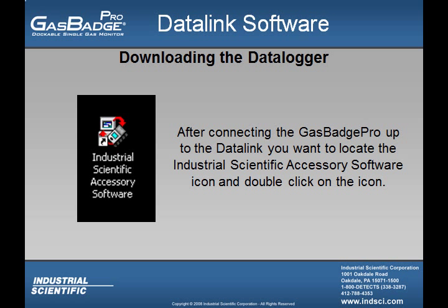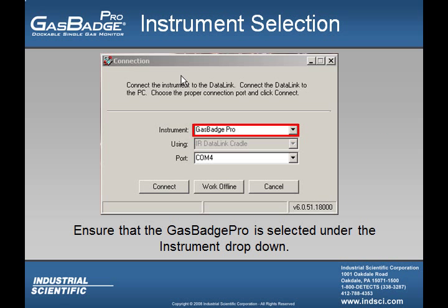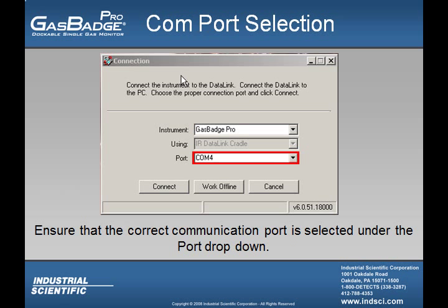After inserting the Gas Badge Pro into the Datalink accessory, the user must locate the Industrial Scientific Accessory Software icon and double-click on it. If the user cannot easily locate the icon, they can press the Start button, click on Programs, locate the Industrial Scientific Accessory Software tab, and click on it. Once the user has clicked on the icon, they want to double-check that the Gas Badge Pro is selected under the Instrument drop-down menu, as well as ensuring that the correct communications port is selected.